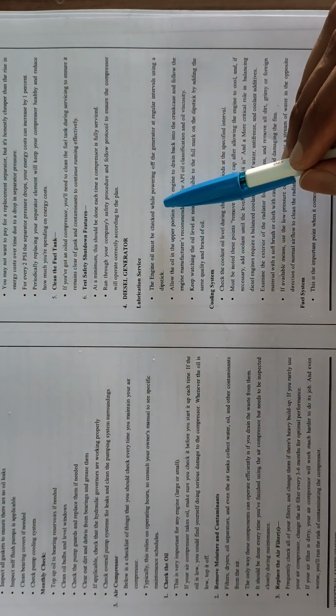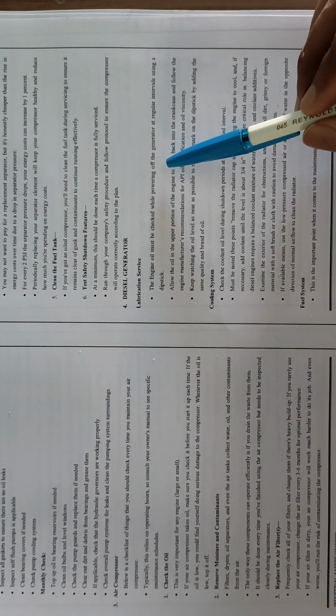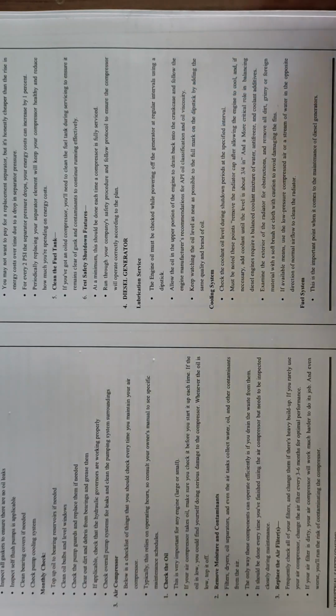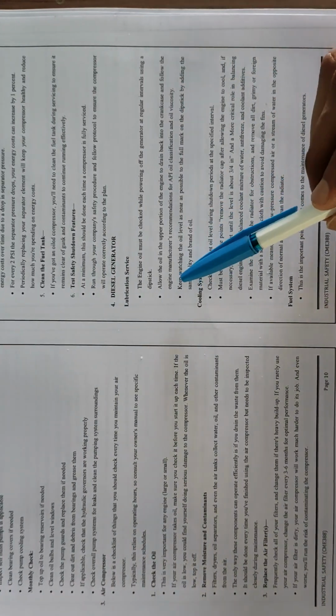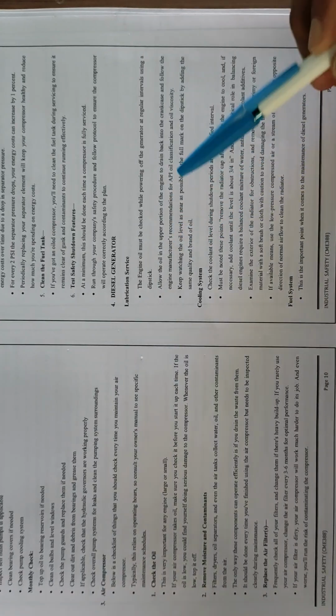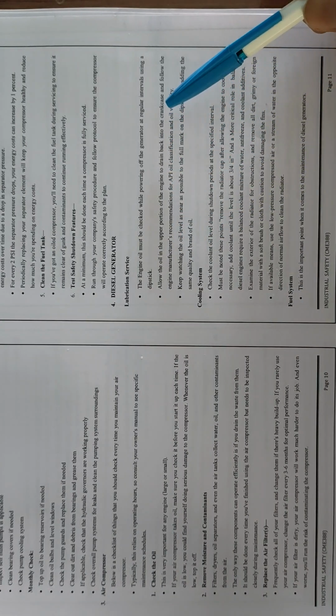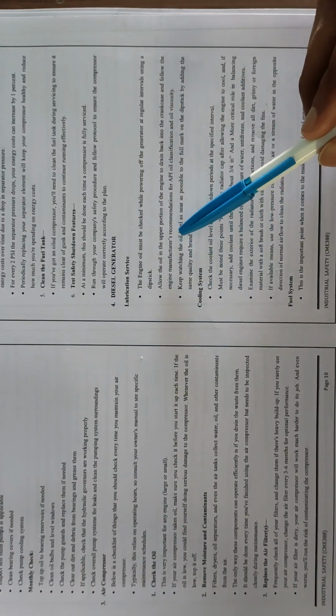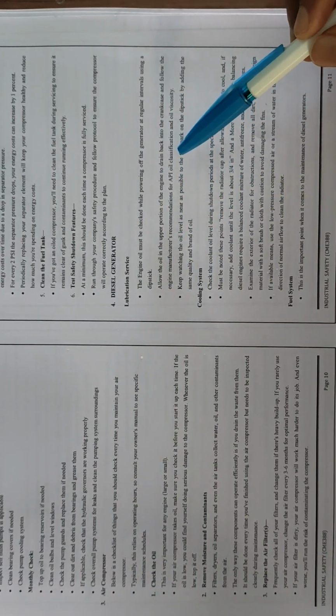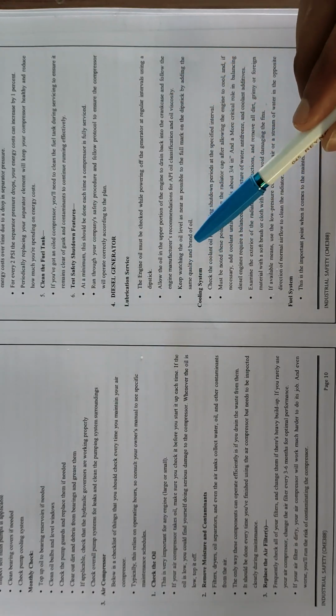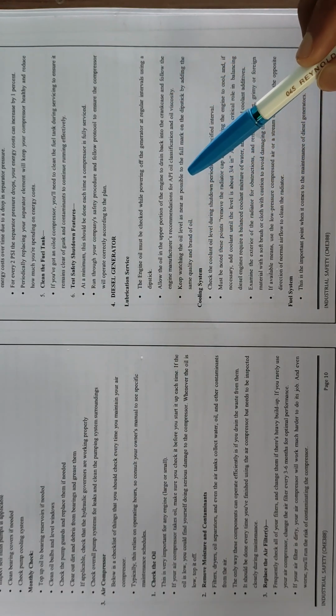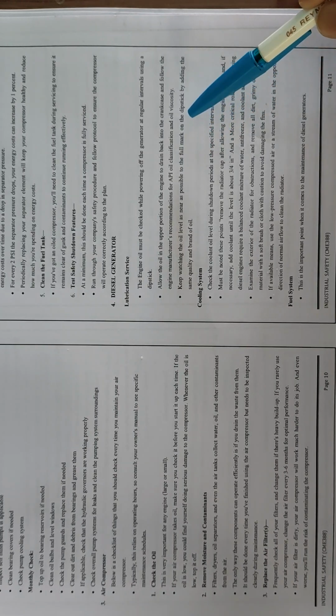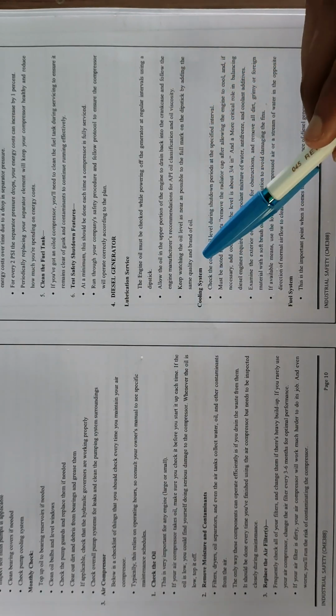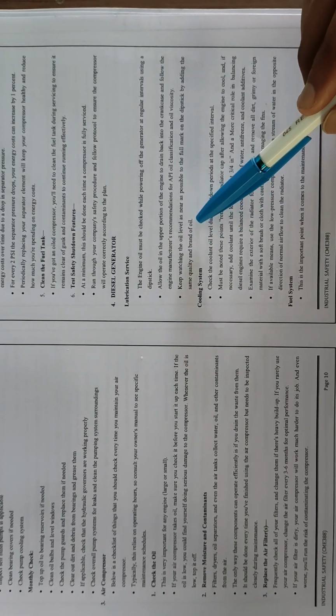Diesel generator lubrication service. The engine oil must be checked at regular intervals with the generator powered off, using a dipstick. Allow the oil in the upper portion of the engine to drain back into the crankcase, and follow the engine manufacturer's recommendations for API oil classification and oil viscosity. Keep the oil level as near as possible to the full mark on the dipstick by adding the same quality and brand of oil.